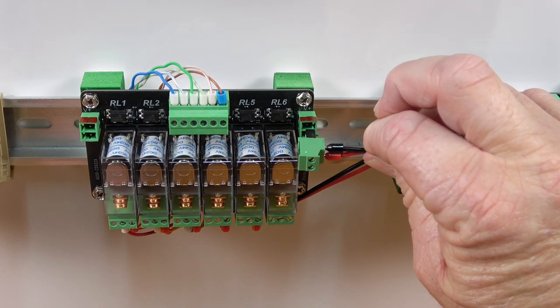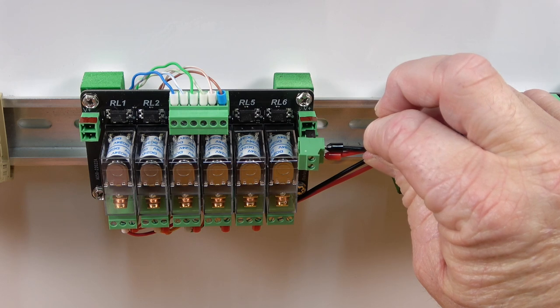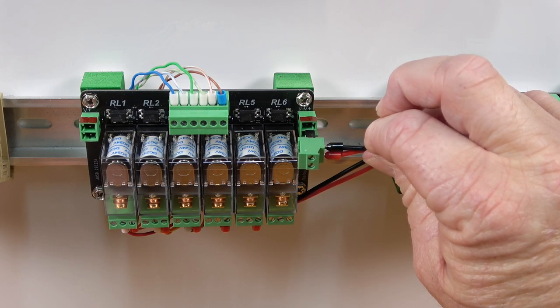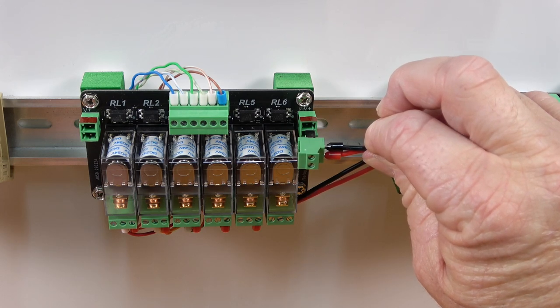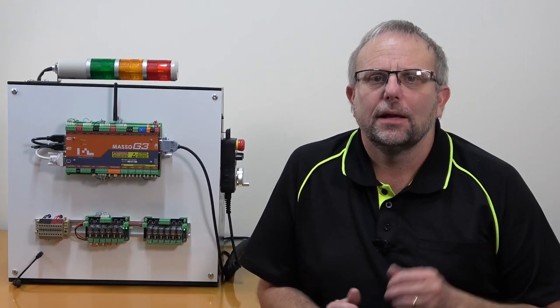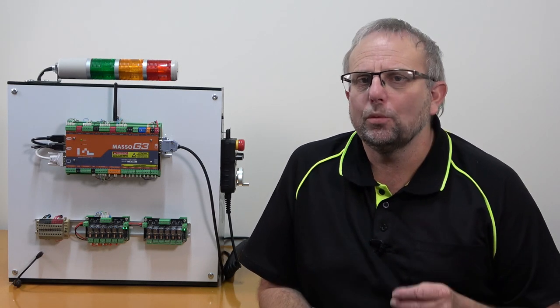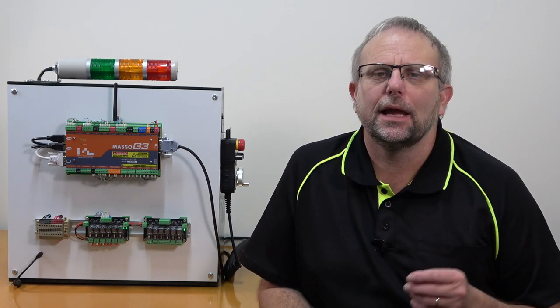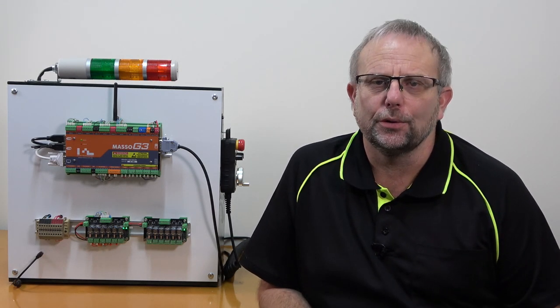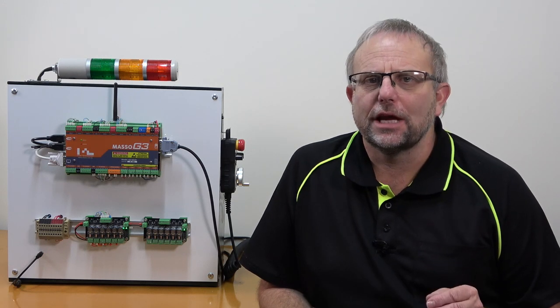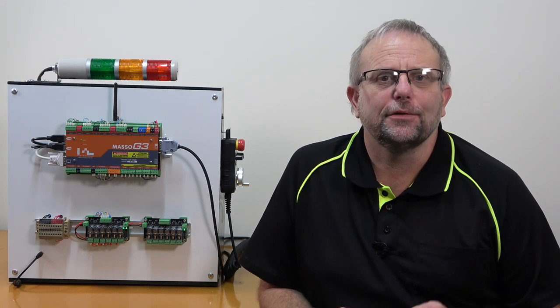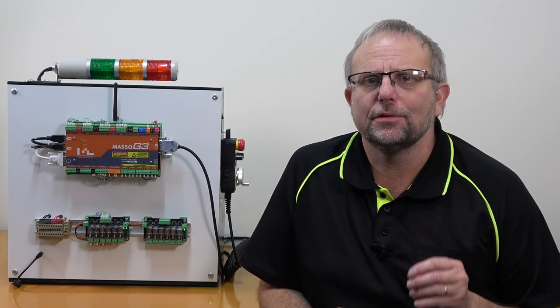Each relay output consists of a normally open, a normally closed, and a common terminal. Each is capable of passing up to 5 amps at 28 volts DC or 5 amps at 240 volts AC.